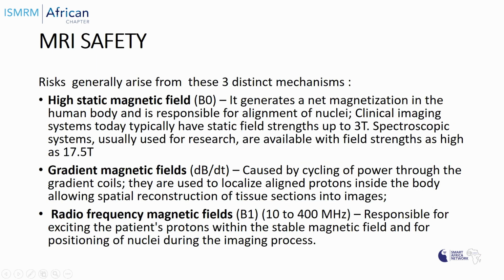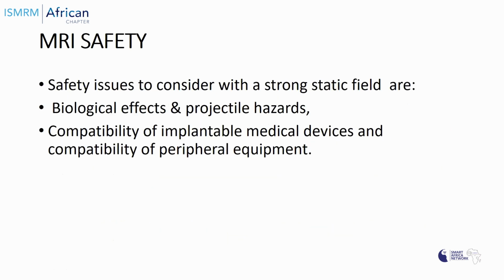Usually, risks generally arise from three distinct mechanisms. We have the high static magnetic field, the gradient magnetic fields, and then the radio frequency magnetic fields. Safety issues to consider with a strong static field are biological effects and projectile hazards. Also, compatibility of implantable medical devices and compatibility of peripheral equipment.